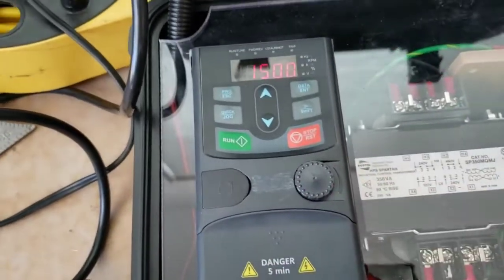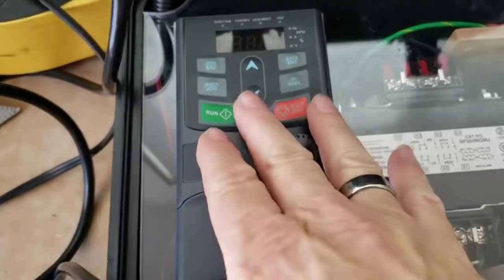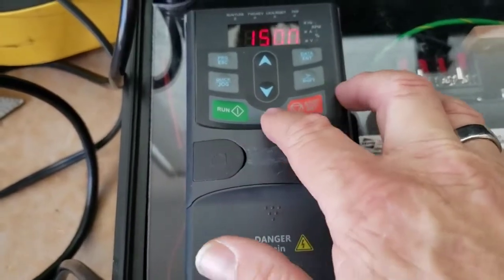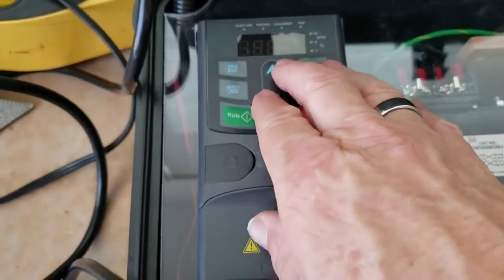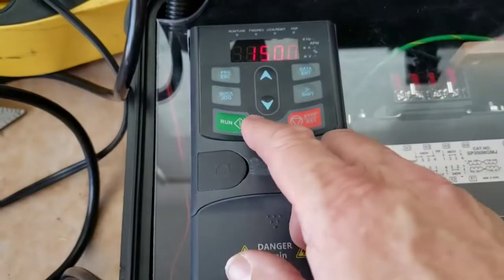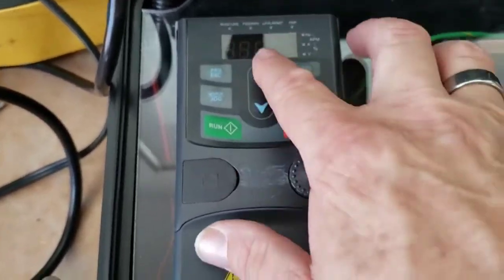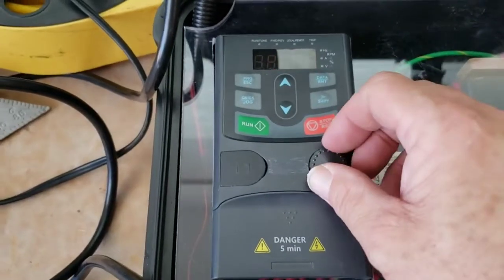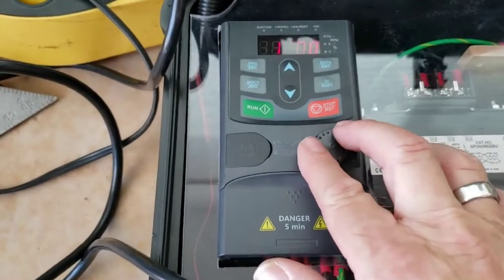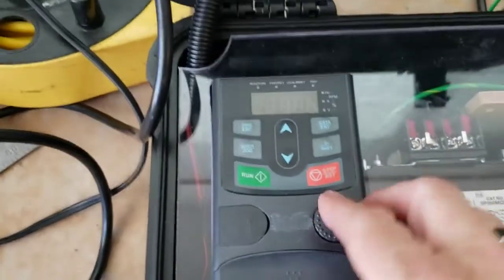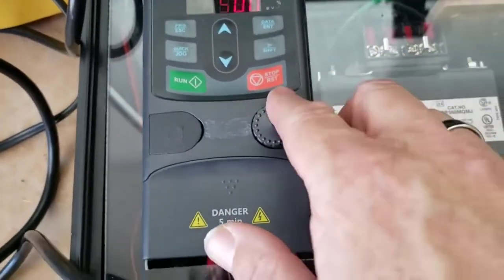With this test box, these things are always going to be up around 7,000 or 8,000 hertz in normal operation, but by doing a sweep, we can enable it to perhaps test other cells. But currently I've got it set for 1500 hertz. So now I've got it up all the way. This one, I know, is going to fail, but in a normal test, you could just turn it all the way up and then see how it reacts.